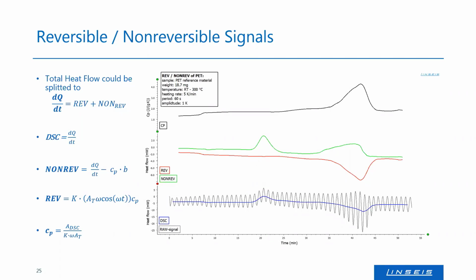So again, some theory. The total heat flow is the reversing heat flow plus the non-reversing heat flow. And so the non-reversing heat flow is the total heat flow minus the CP multiplied with the heating rate, and the reversing heat flow is the calibration factor multiplied with the amplitude multiplied with omega, the cosine of omega and time, and of course the CP. So this is how we get the value of the CP.